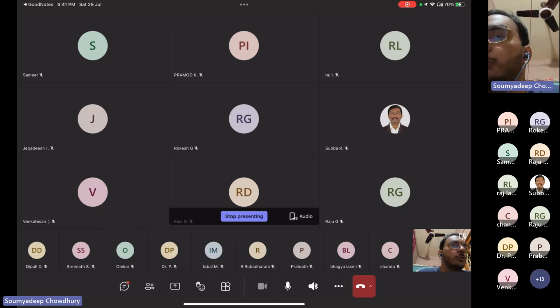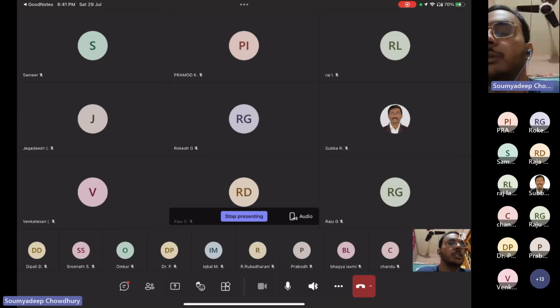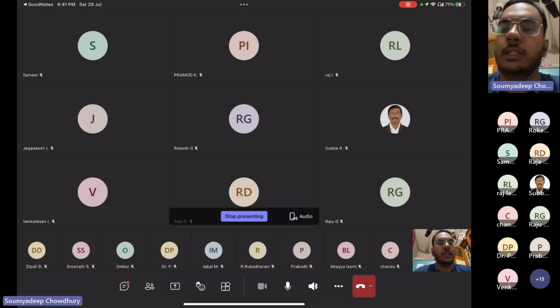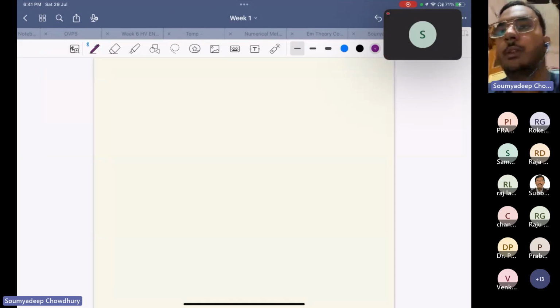So within this 1.2 microsecond, this sudden increase in the voltage, this dV by dt, change in voltage divided by the change in time, is of the order of 10 to the power 9. Not even 10 to the power 9, 10 to the power 12. The dV by dt will go of the order of 10 to the power 12 volt per second, which is very huge. So this rate of rise of voltage or rate of rise of current is one of the most important factors because of which we need to take care of the power system equipment. One second, I'll write it down.